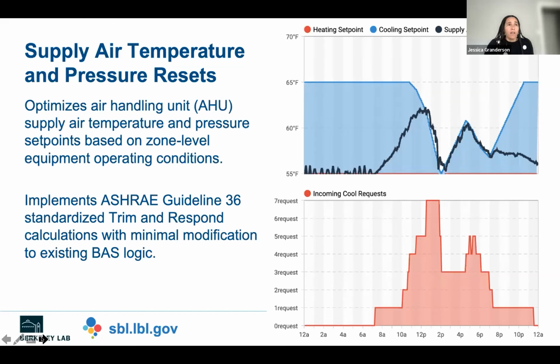We've implemented automated routines. So with the push of a button, we can deploy 2 different types of BAS. The ASHRAE Guideline 36 standardized trim and respond to do supply air temperature and supply air pressure resets across air handling units. And so in these plots on the right, I show on the top the cooling set point in blue, the supply air temperature in black on the top, and on the bottom, in red, the cooling requests throughout the course of the day.